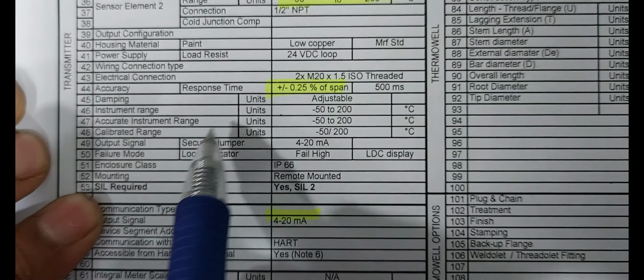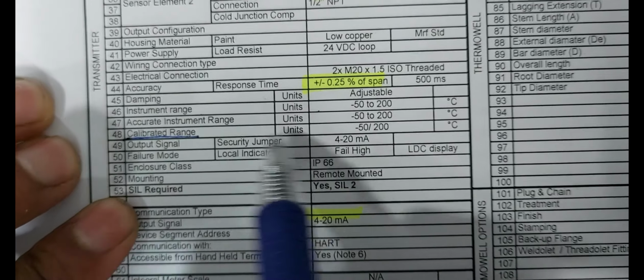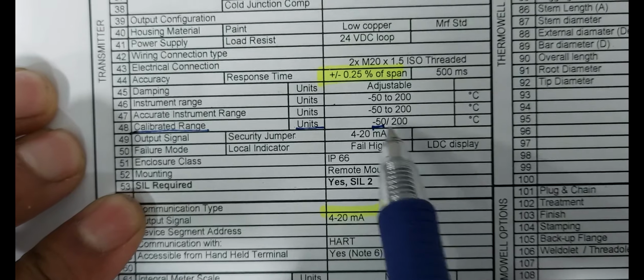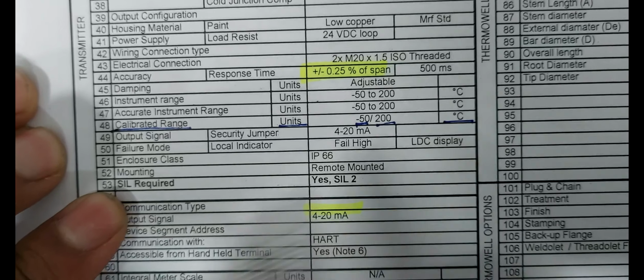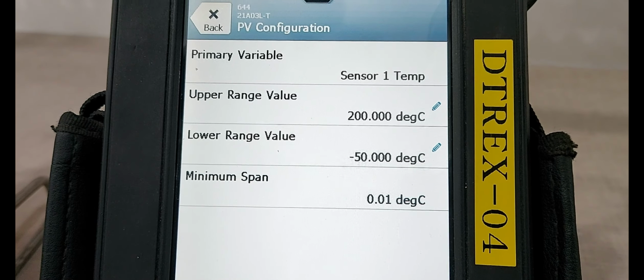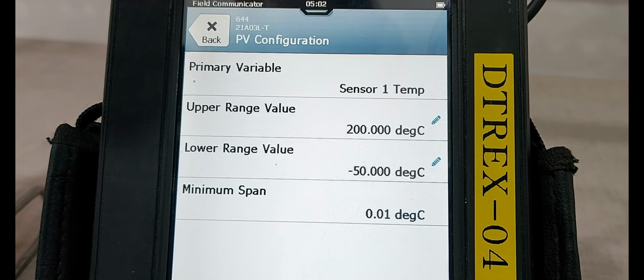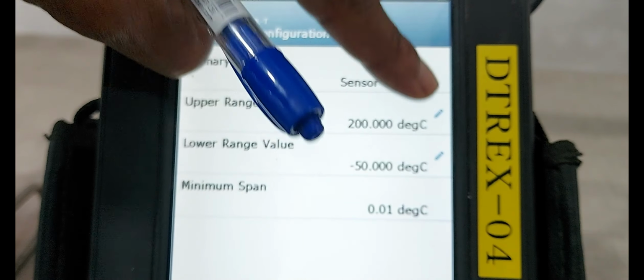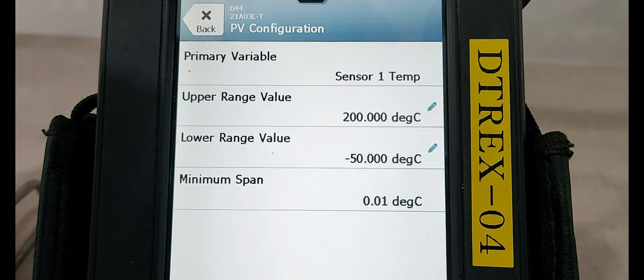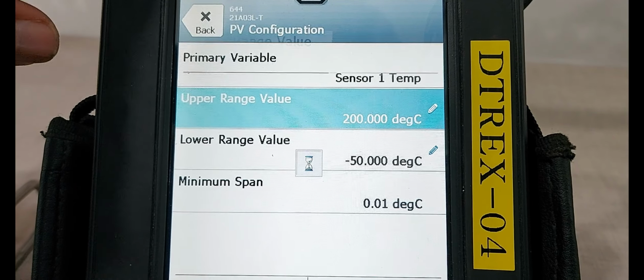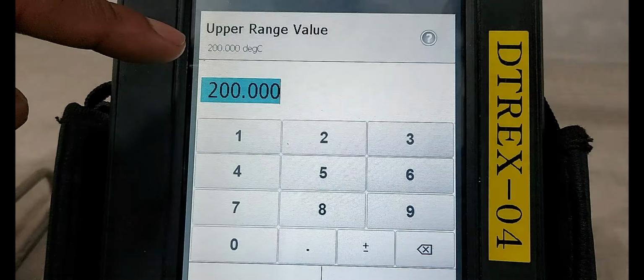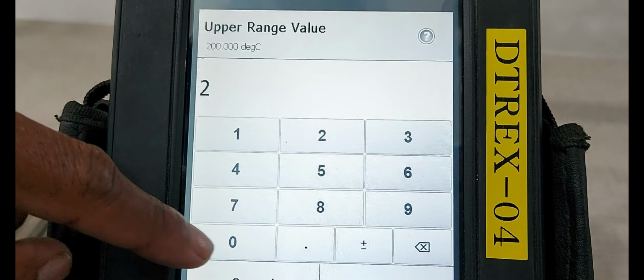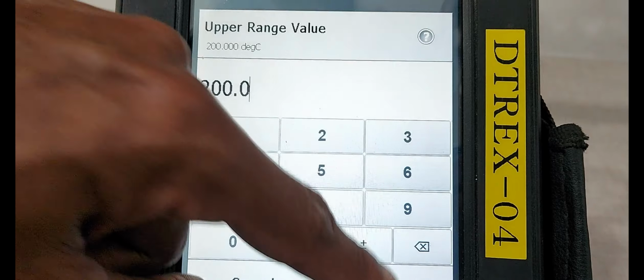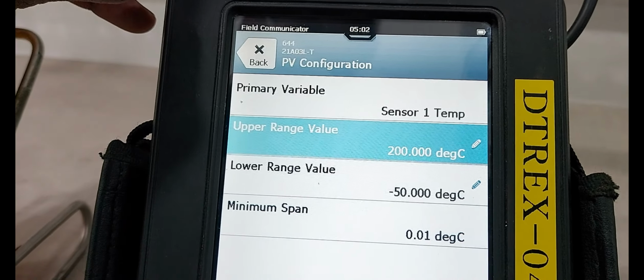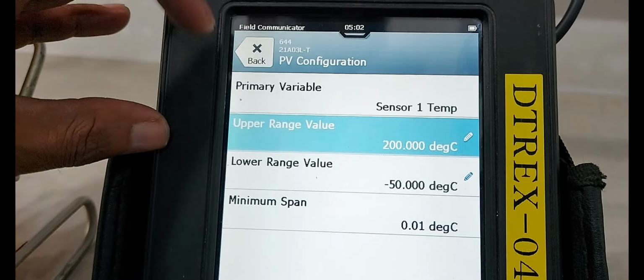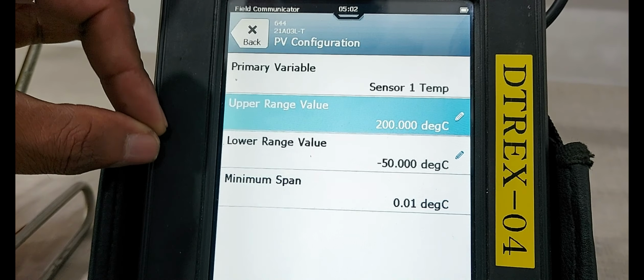As per the data sheet, instrument calibration range showing minus 50 to 200 degree. If you need editing, this pencil arrow is the editing option. Okay, if you press it you can change the values. Manufacturer already configured 200 degree. This is the procedure for changing the LRV and URV parameters.